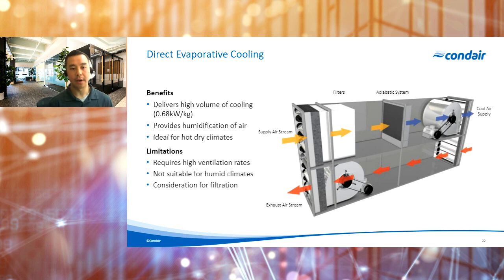Now, the other consideration here with this type of system is on the filtration side. Because we're bringing in a lot of fresh air, it's important to make sure that we do have proper filtration here to keep out any kind of outside particulates or contaminants from entering that supply air stream.